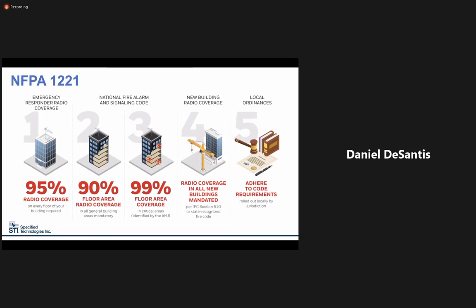The National Fire Alarm and Signaling Code has a slightly different standard. They require that 90% of general building square footage must be covered and 99% of critical areas such as fire pump rooms. Paths of egress and stair towers must also be covered. It's important to consult with your AHJ on the project to gain a clearer perspective on what's required.